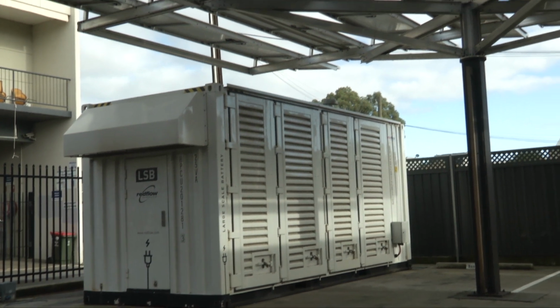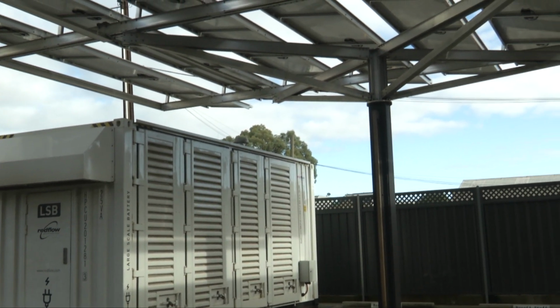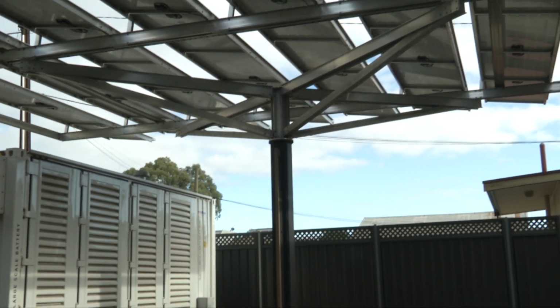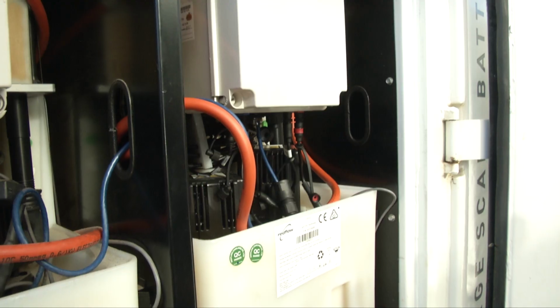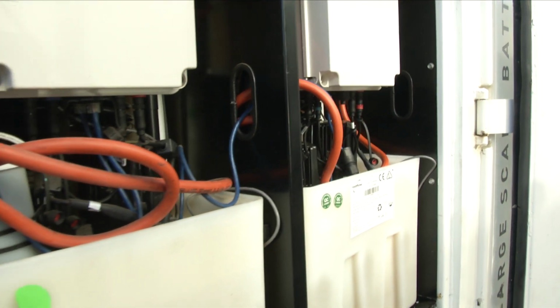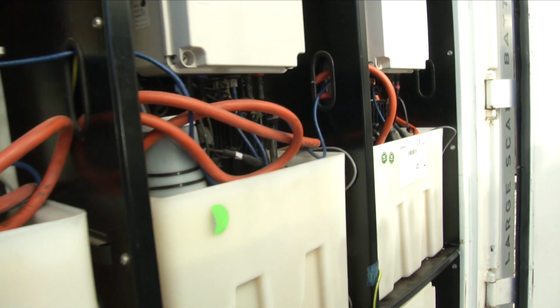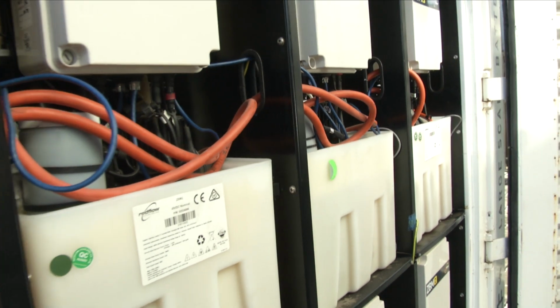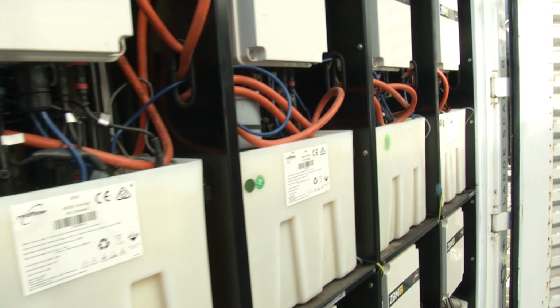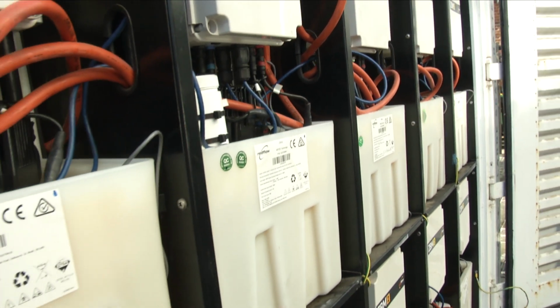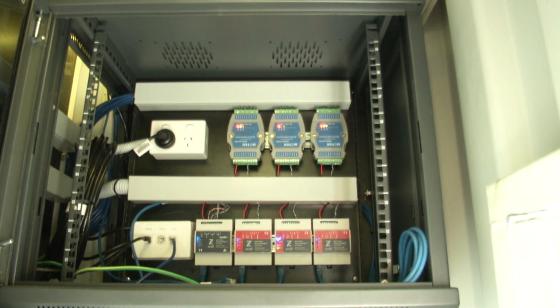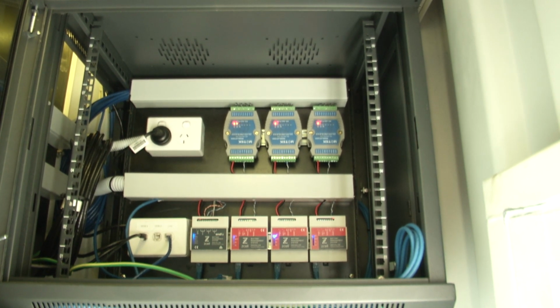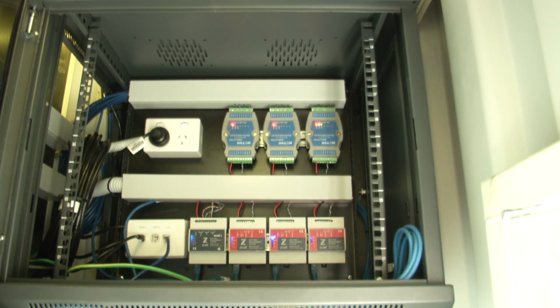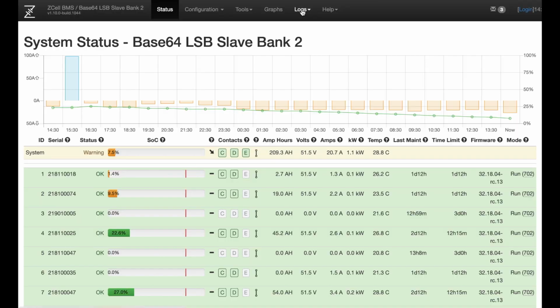You can also have spare batteries that are ready to use, but are almost completely shut down so their pumps and fans are not running. Perhaps most importantly, the BMS can use the standby mode to hide the maintenance cycles of your ZBMs, which lets an array of ZBMs operate just like a lithium or lead acid battery bank, but with more flexibility, availability, and operating life. The Redflow BMS turns a set of ZBMs into an energy storage appliance.